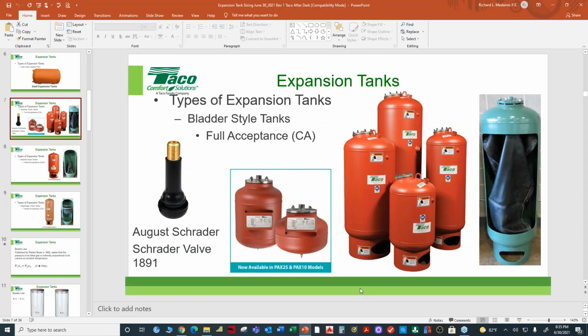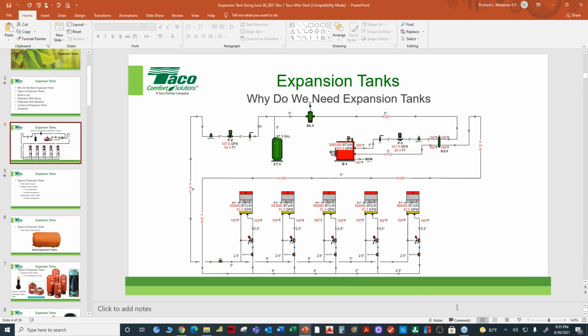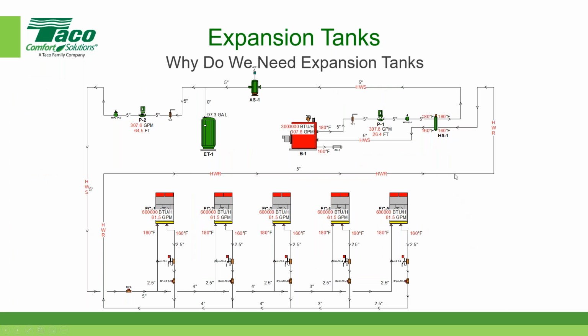Let's go look at another diagram here. In this case, you'll notice we have a primary pump and a secondary pump, and the expansion tank is located here. This piping connection right here is called a point of no pressure change, and it's very close to the suction side of the pump. We only want that expansion tank in one location, because if you put two expansion tanks at two different locations, they will tend to fight each other. If you put multiple tanks, you want to connect them all to the same location in the piping system. So if I put three expansion tanks in there, well, that's a gross looking expansion tank, isn't it? The Taco ones do not look like that. How do we say that? Don't do that.